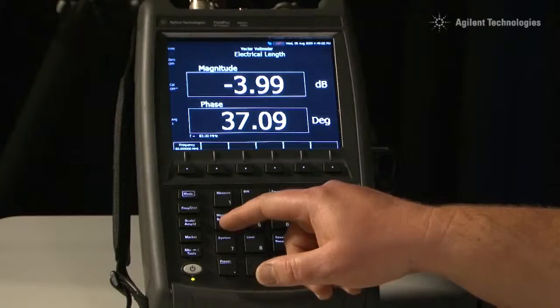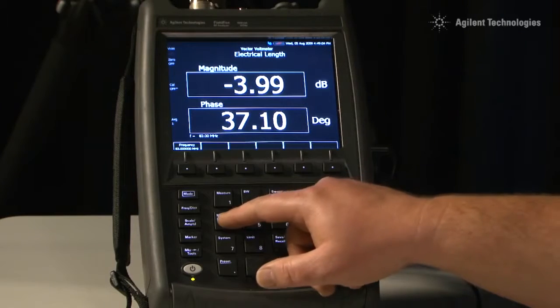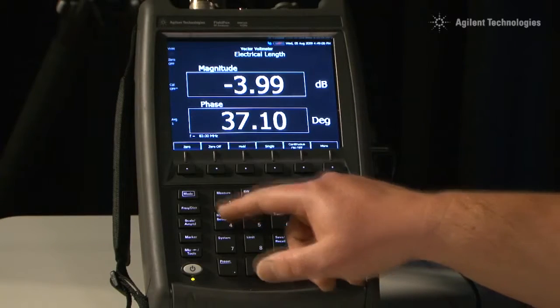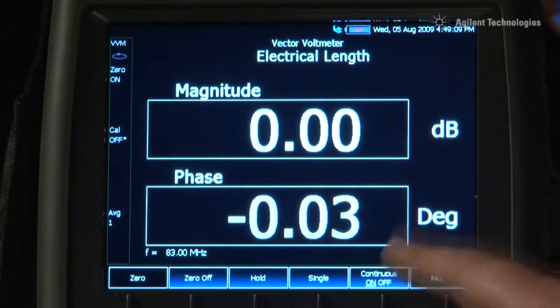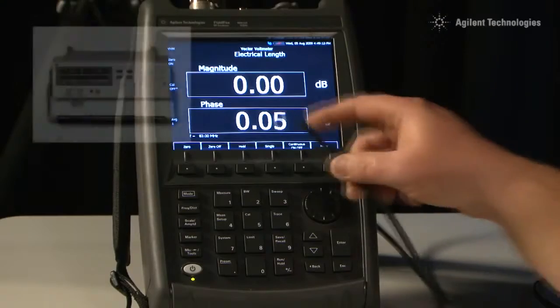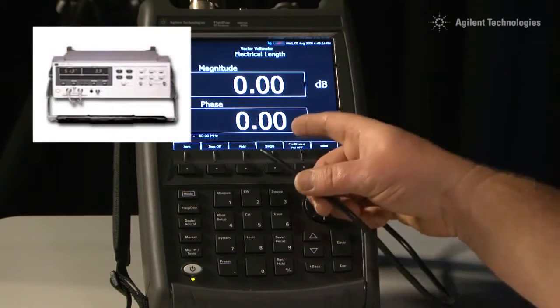The Vector Voltmeter option lets us compare the electrical length of devices. For example, we can accurately phase trim cables for radar and direction finding systems, producing matched pairs with the same electrical length and phase delay, just like we did with the old HP8508A Vector Voltmeter.